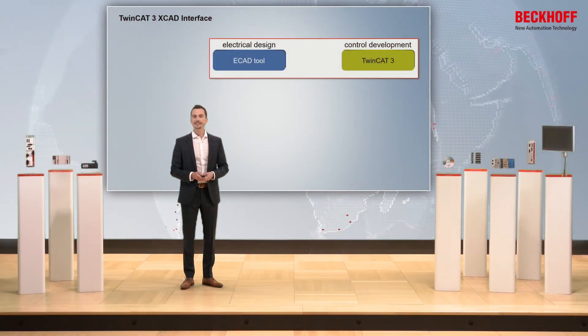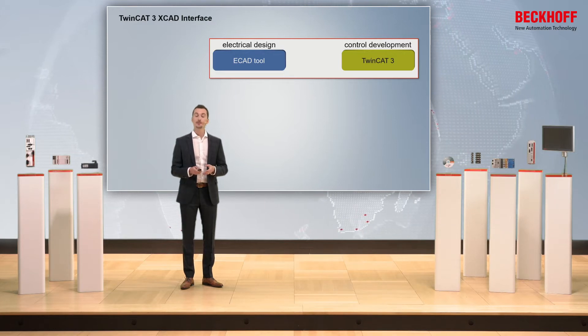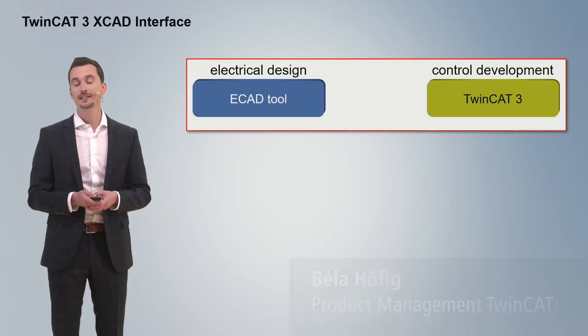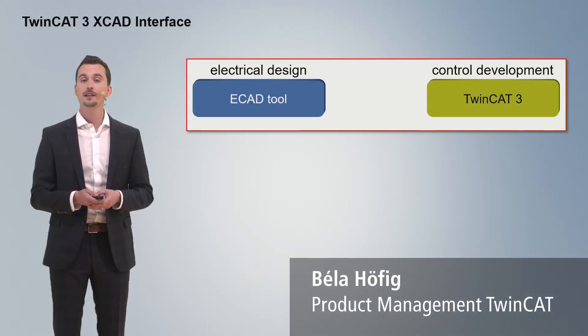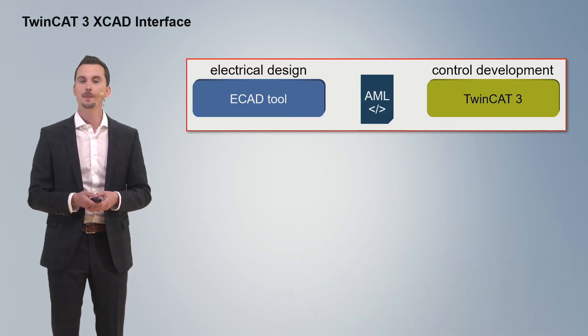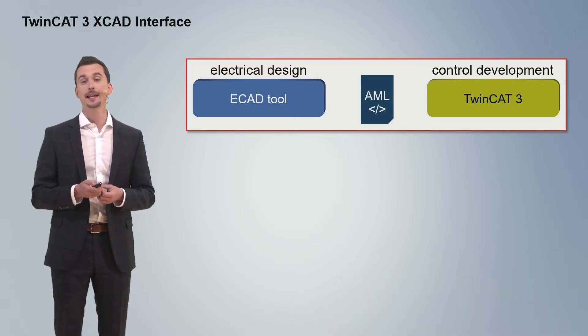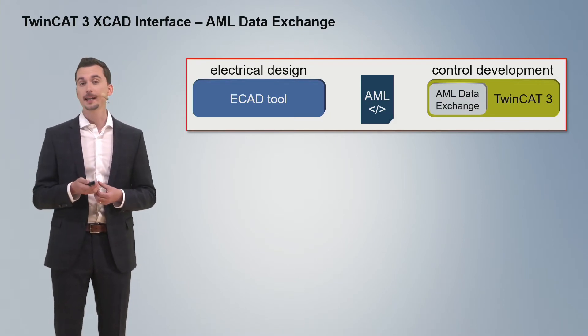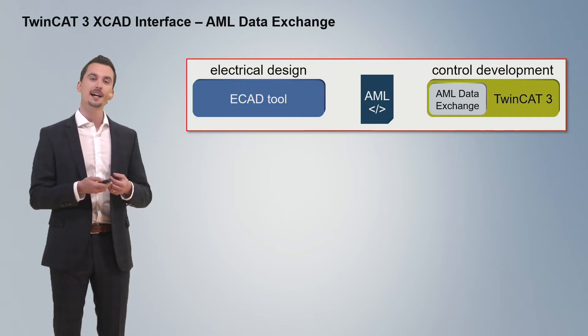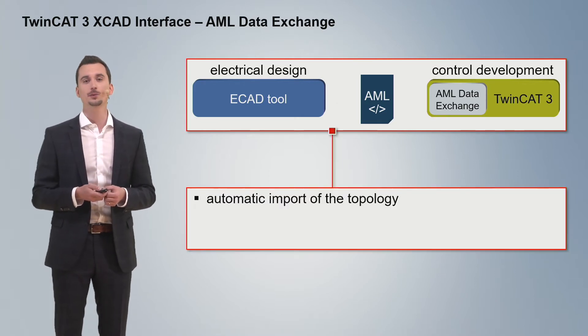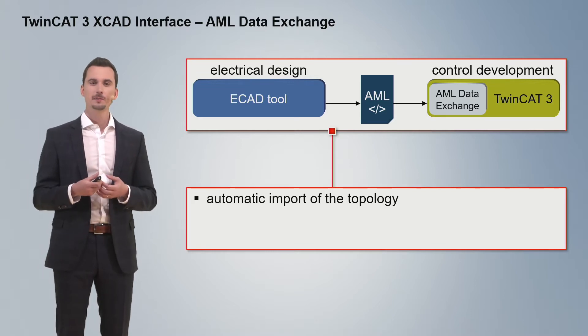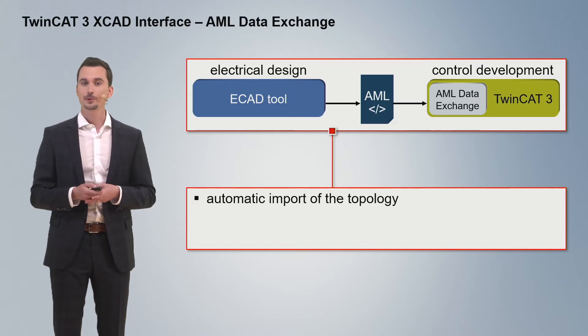With the TwinCAT 3 XCAD interface, you can easily exchange IO topology data between the electrical design and the software development. The new version is based on a standardized exchange format, the so-called AutomationML, and a new basic component in TwinCAD, the AML Data Exchange. This component enables you to import an already existing IO topology into your TwinCAD project, which means the IO topology is automatically added to your TwinCAD project.